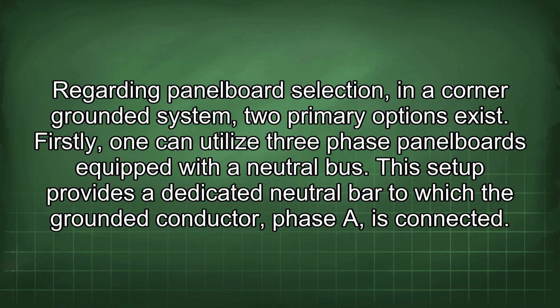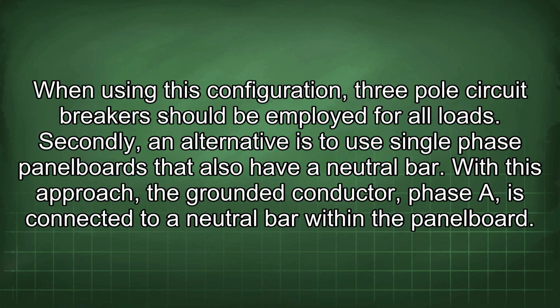Regarding panel board selection, in a corner-grounded system, 2 primary options exist. Firstly, one can utilize 3-phase panel boards equipped with a neutral bus. This setup provides a dedicated neutral bar to which the grounded conductor, phase A, is connected. When using this configuration, 3-pole circuit breakers should be employed for all loads.